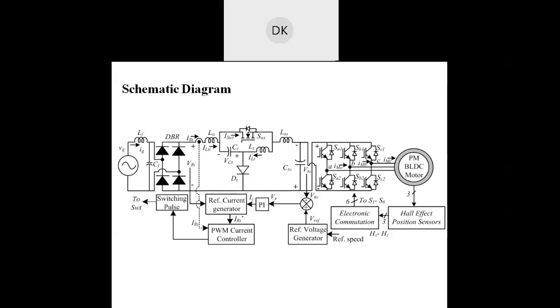In voltage source inverter, in fundamental switching we are using IGBTs operating at fundamental switching frequencies, so the overall cost of these IGBTs will be very low, since you require very low frequency IGBTs. These are spare IGBTs available with all companies, and their cost is very low compared to high frequency IGBTs. This fundamentally reduces cost, reduces switching losses, and improves efficiency. Now you only require one good quality IGBT capable of operating at high frequency, and the dynamic response is also significantly improved since you only need to change the switching sequence of one IGBT to track any sudden change on the load side.